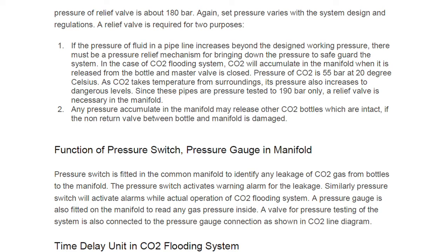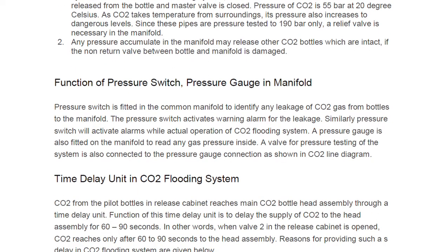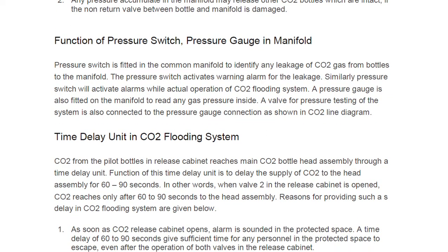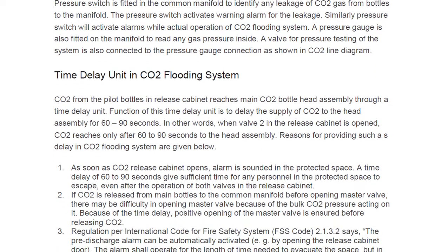The pressure switch is fitted in the common manifold to identify any leakage of CO2 gas from bottles. You may see a white-colored box directly mounted on the line — that is the pressure switch. The pressure switch activates a warning alarm for leakage, and will also activate alarms during actual operation of the CO2 flooding system. A pressure gauge is also fitted on the manifold to read any gas pressure inside. A valve for pressure testing of the system is also connected to the pressure gauge connection.